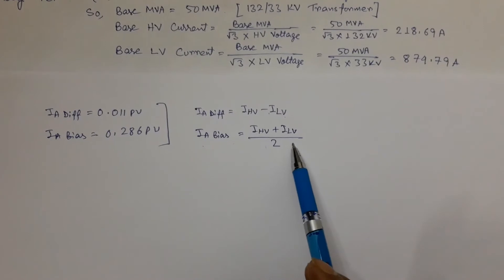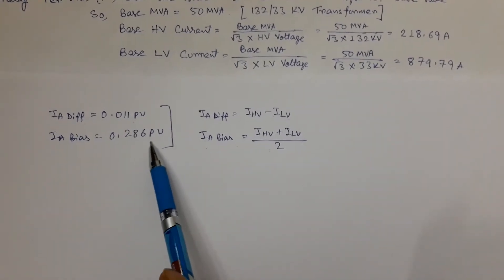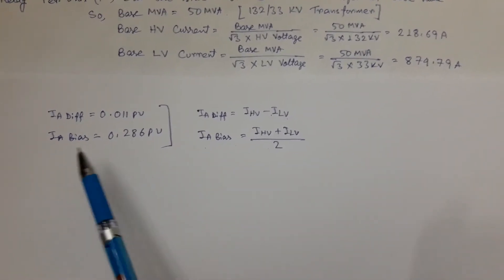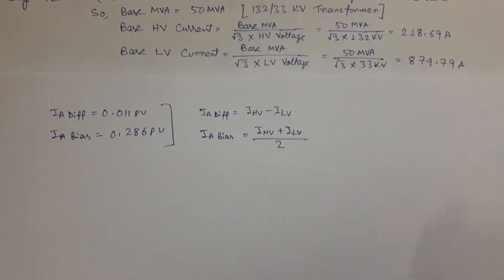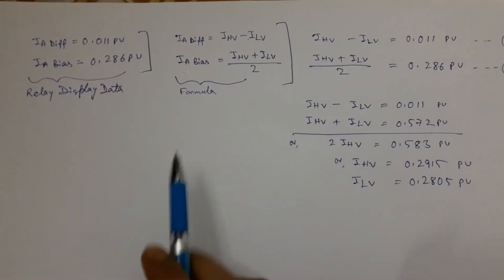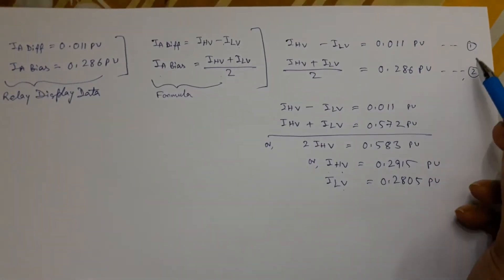We get these two values of differential and bias current in respect of A phase from relay display. So by using this formula and these relay data, we can write these two equations.